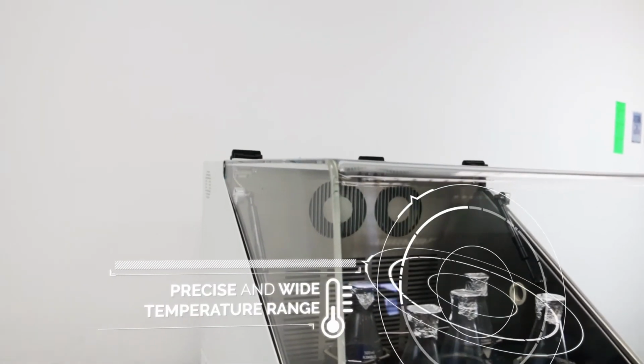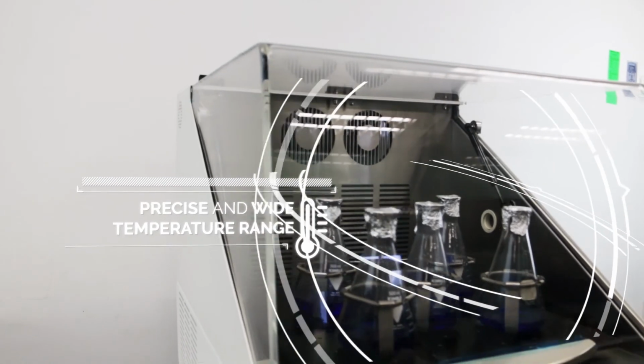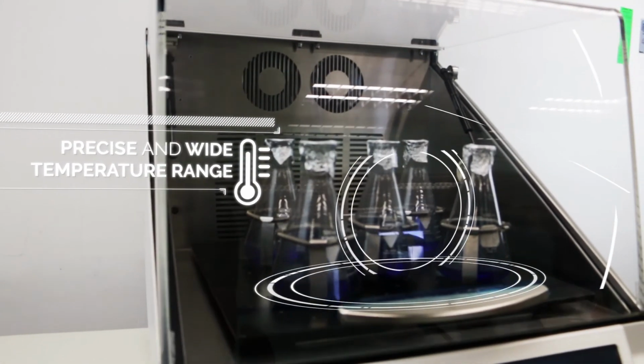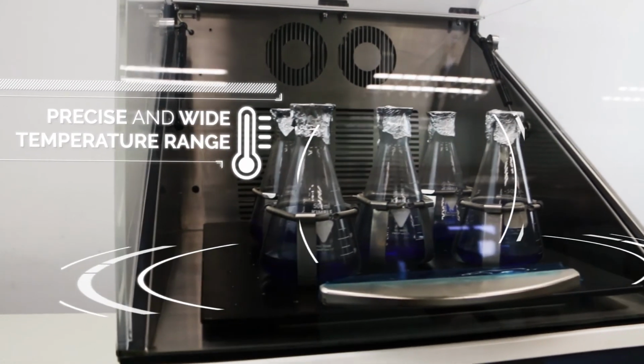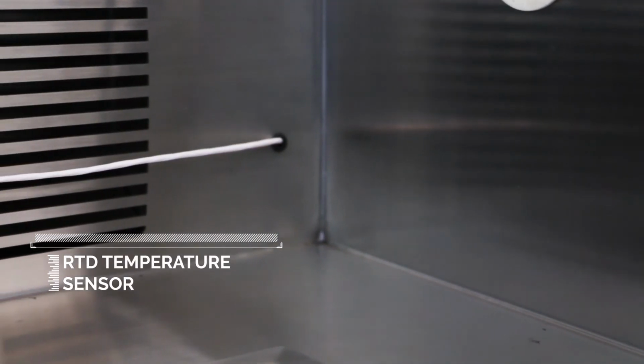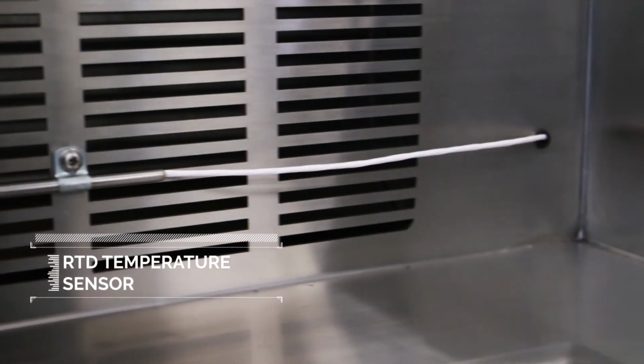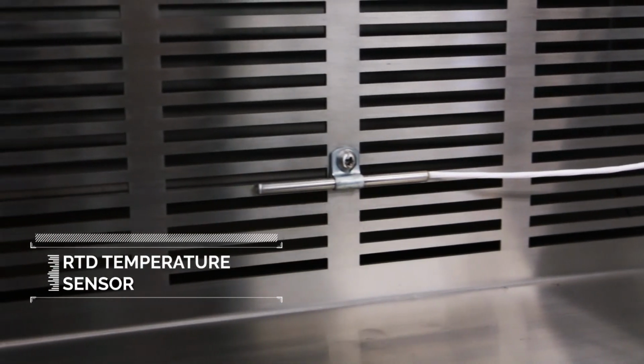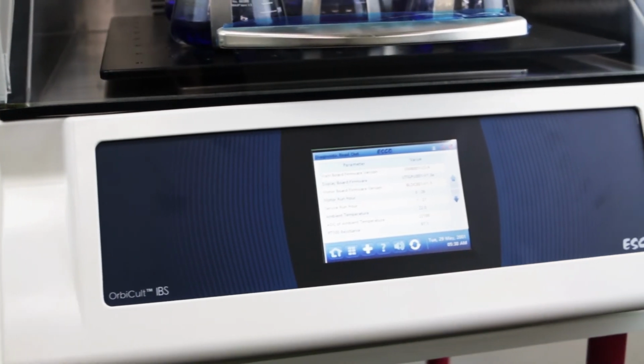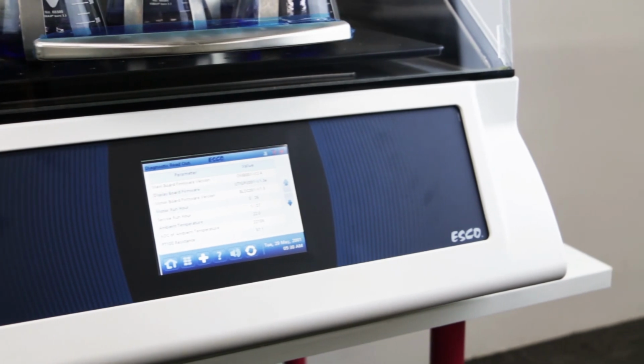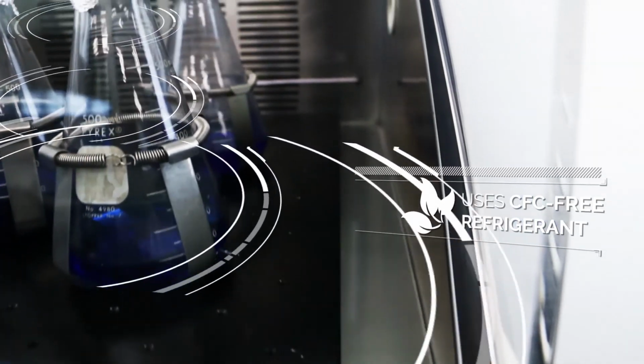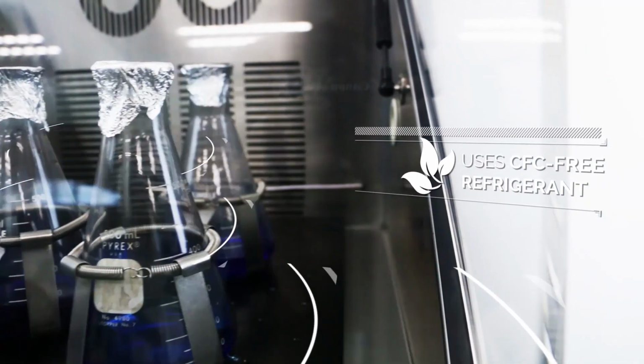Precise and wide temperature range of the OrbiCult Incubator Benchtop Shaker ensures accurate temperature, avoiding possible deviations during the operation. RTD temperature sensor stops the compressor in any exceeded temperature. Environment-friendly refrigeration system of the OrbiCult Incubator Shaker uses CFC-free refrigerant, which is good for the environment.